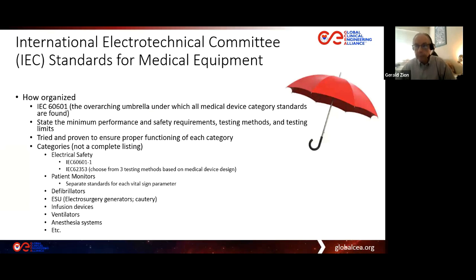For medical equipment, these fall under the umbrella of IEC 60601. It is the overarching umbrella under which all the medical device category standards are found, and the 2 electrical safety standards. They are all underneath this umbrella. So one of the things that I often have to catch people about is when they want to talk about electrical safety, they don't want to say the entire electrical safety standard name. And so they just say, or publish in the service manual test procedure, IEC 60601. Well, that only refers to the umbrella. It doesn't tell us which standard under 60601.